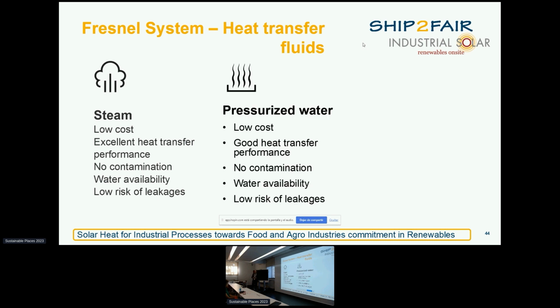The second option is pressurized water. For example, some breweries also use pressurized water, which means water above 100 degrees Celsius. Of course, water below 100 degrees Celsius is also pumped with pressure, but in this case, we call it superheated water. It's also low cost. Of course, in this case, the energy usage for the pump is a little bit higher because you need higher pressure than what we have for this system. The heat transfer performance is not as good as steam, but it's also quite good. And no contamination, water availability, and risk of leakage are similar to steam.